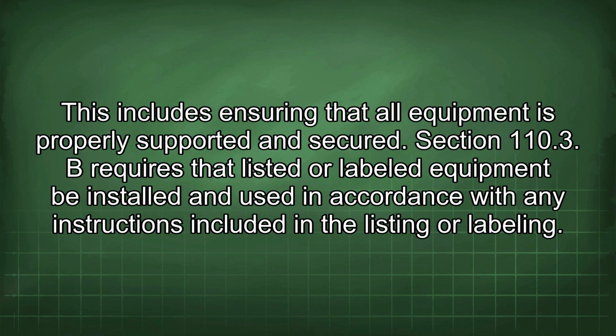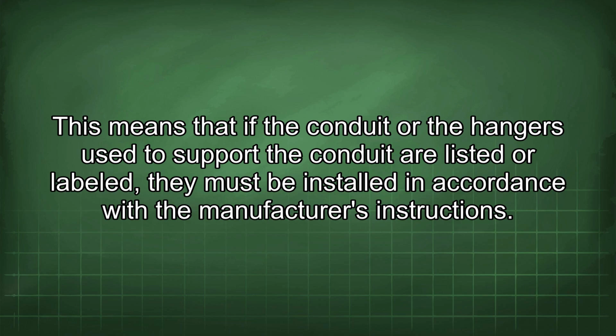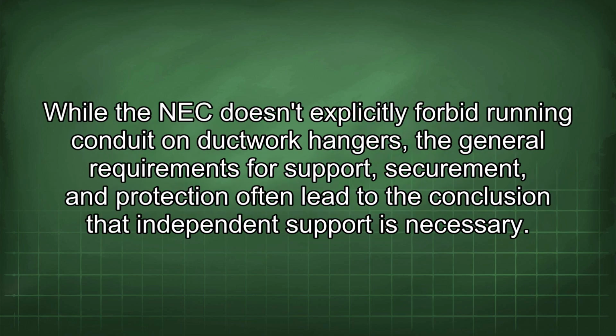Section 110.3 B requires that listed or labeled equipment be installed and used in accordance with any instructions included in the listing or labeling. This means that if the conduit or the hangers used to support the conduit are listed or labeled, they must be installed in accordance with the manufacturer's instructions. While the NEC doesn't explicitly forbid running conduit on ductwork hangers, the general requirements for support, securement, and protection often lead to the conclusion that independent support is necessary.